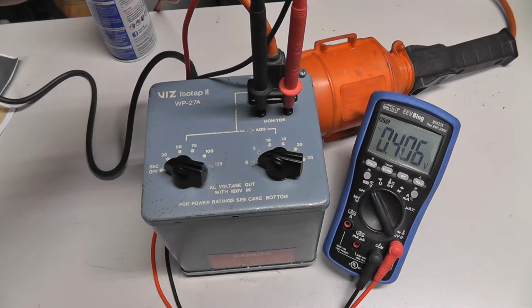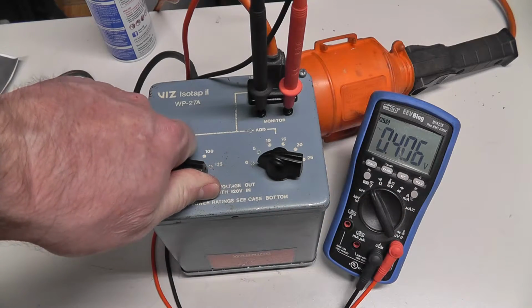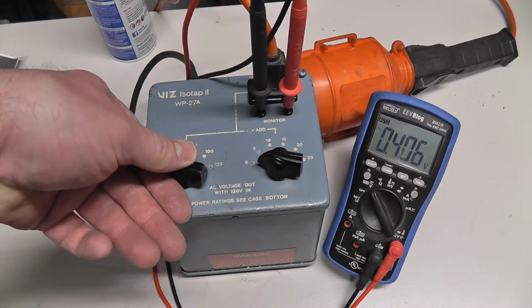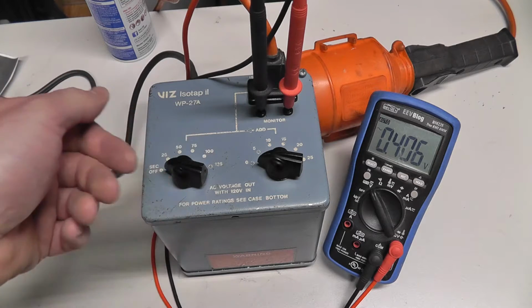With the load on, the secondary off is working, it goes all the way down to 0.4 volts, which is basically what we saw going from neutral to earth ground.